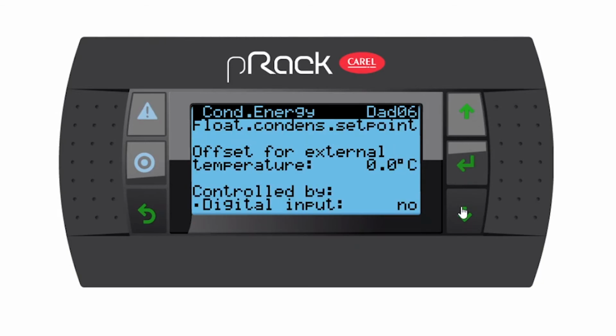Go down. Floating condensing set point, offset for external temperature. So how much higher do you want the condensing set point to be above external temperature? And then as the external temperature goes down, your set point will go down as well. So I would say a 5 degree will be a good set point to have. Don't go too low, and obviously if you go too much, it defeats the object. So let's go 5 degrees.